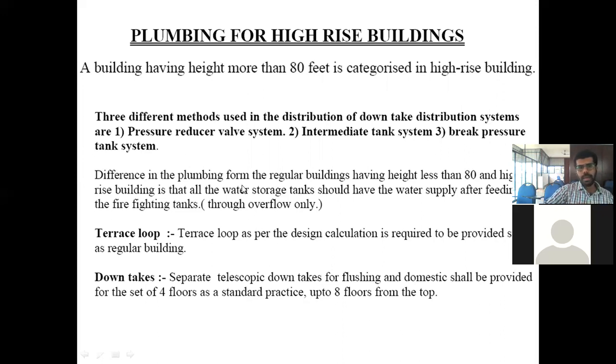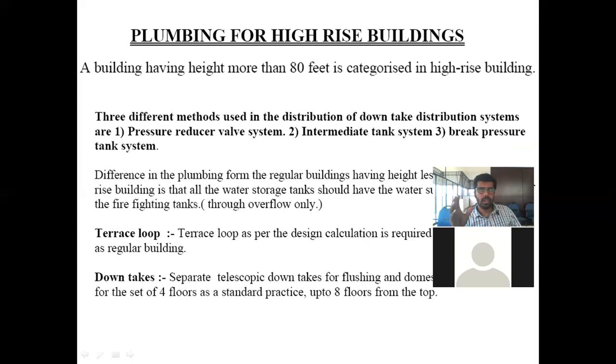So the difference in the plumbing between regular buildings having height less than 80 feet and high-rise buildings is that the water storage tank should get its water supply only after feeding the firefighting tanks, through overflow only. What does this mean? In a high-rise building you have to keep this in mind: firefighting is very important. Fire system is very important.